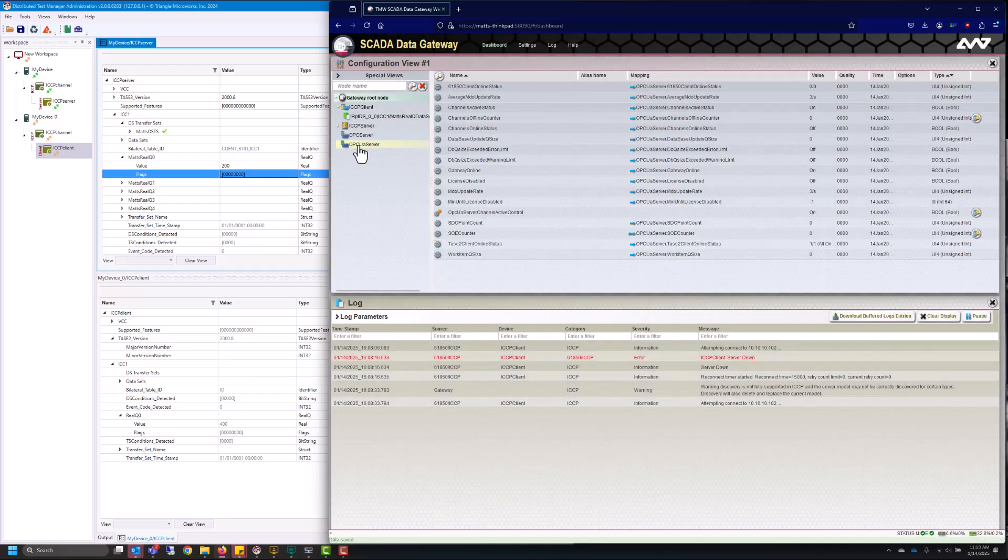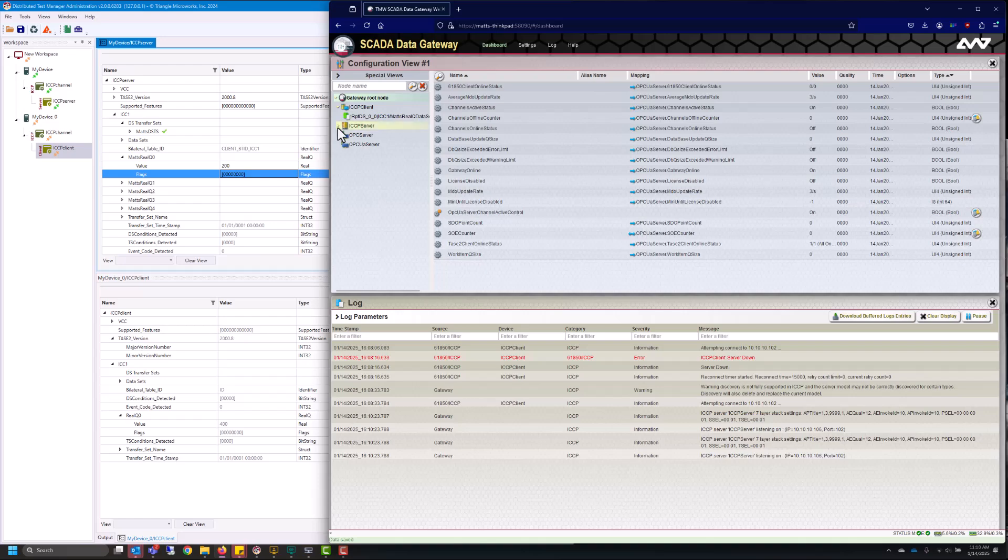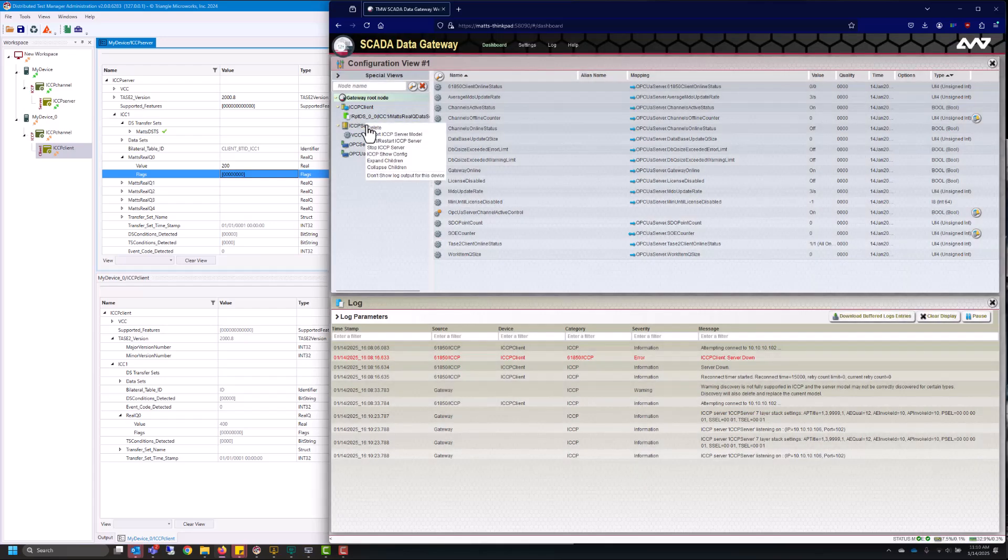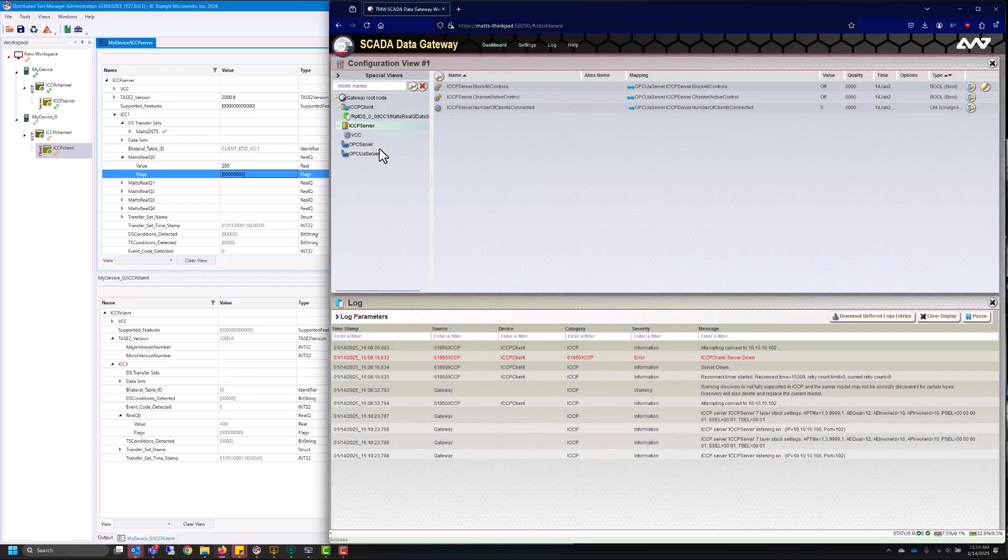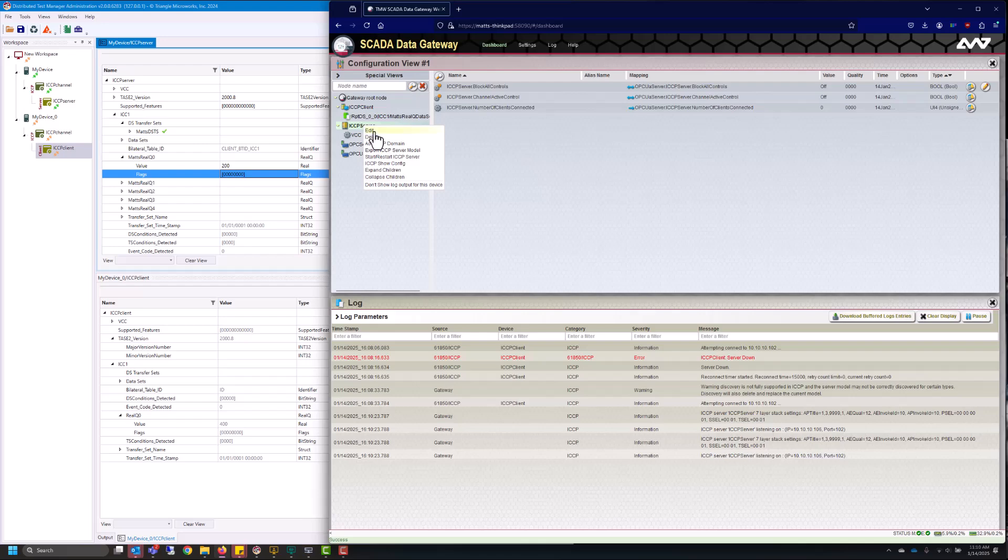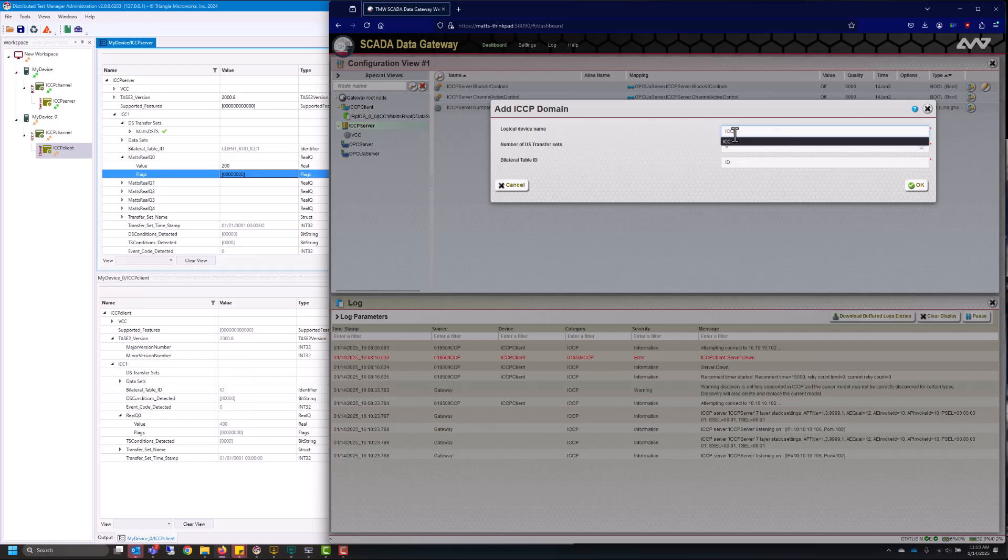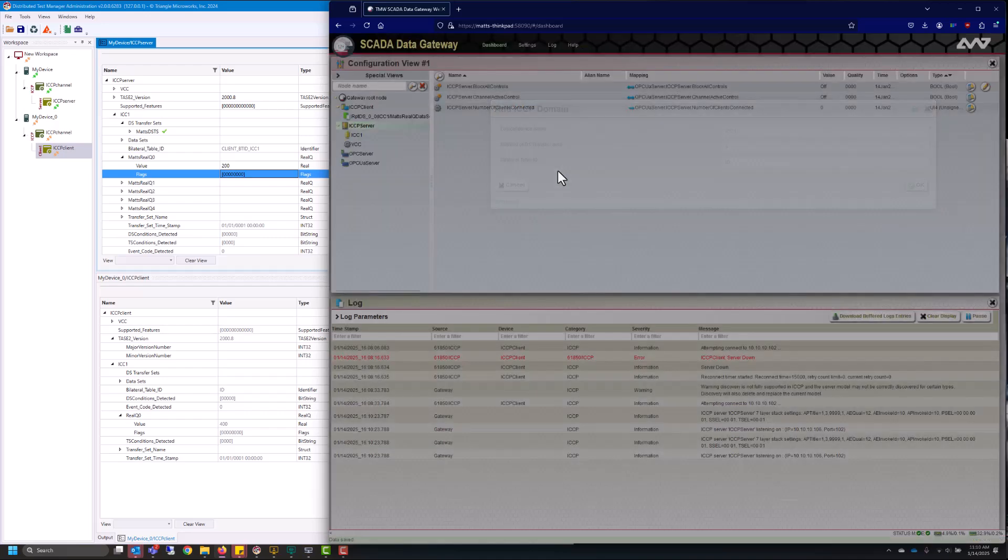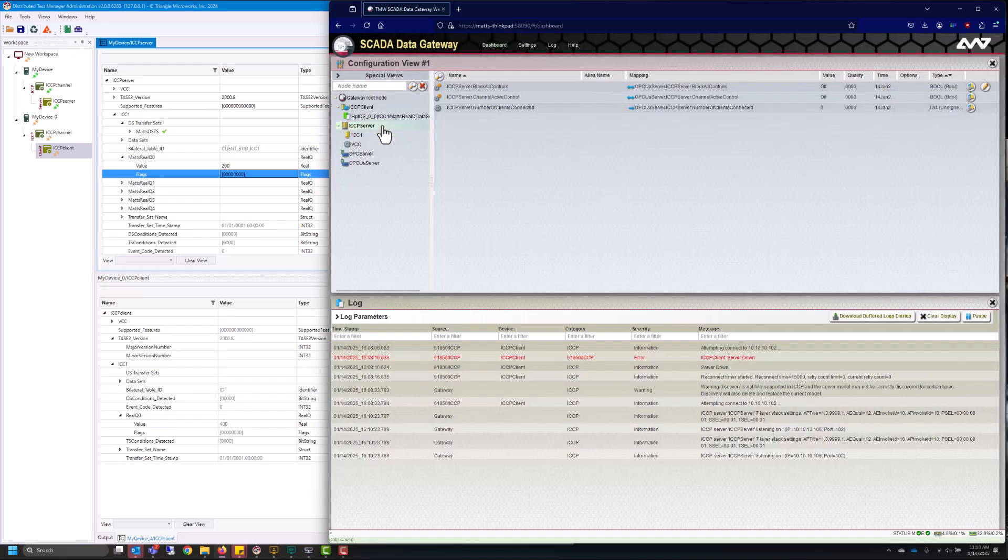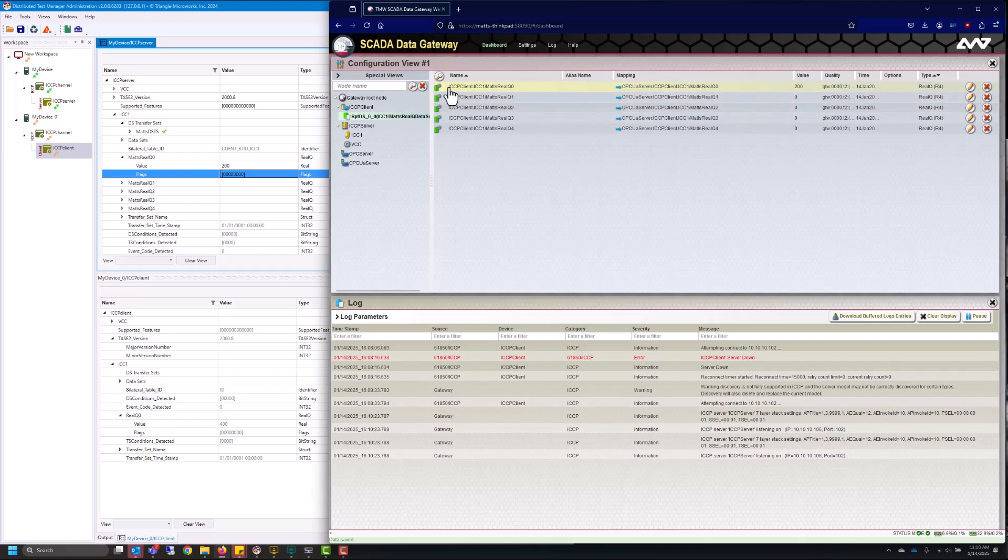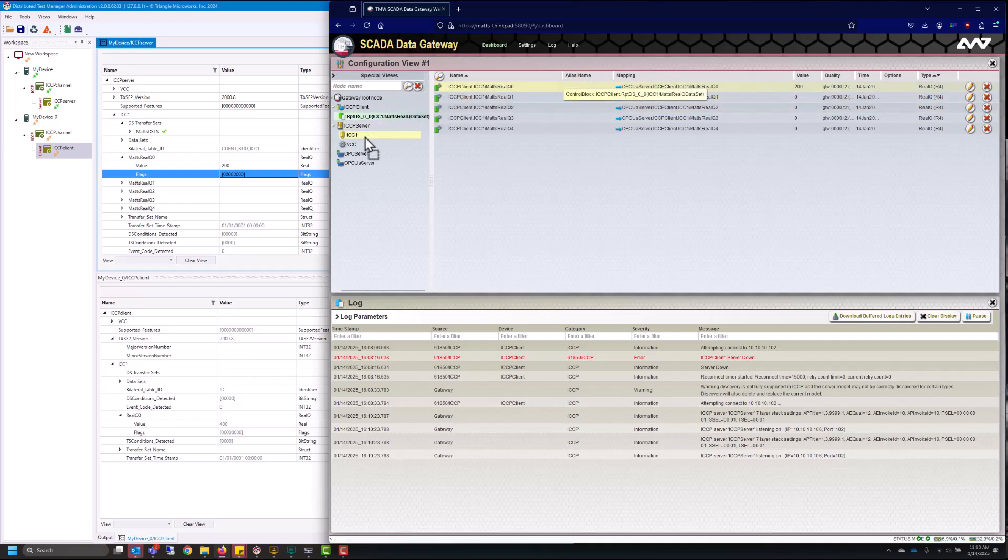Now we have an ICCP server here we need to go ahead and get the value from our client over to our server. So I'll stop the server that way I can change the model and I'll go ahead and add a new domain and like the one from before I'll name this ICC1. The number of data set transfer sets is default set to 5 which is fine for my case.